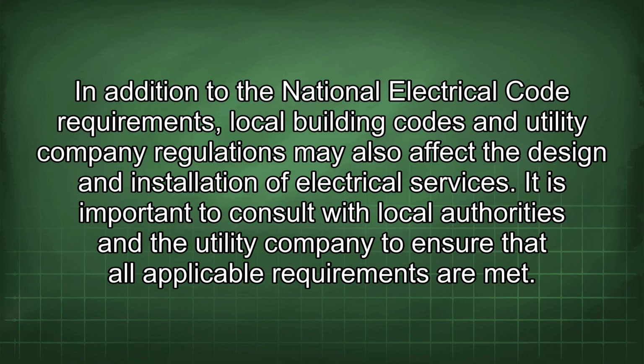The size and type of overcurrent protection device must be carefully selected to match the ampacity of the service conductors. In addition to the National Electrical Code requirements, local building codes and utility company regulations may also affect the design and installation of electrical services. It is important to consult with local authorities and the utility company to ensure that all applicable requirements are met.